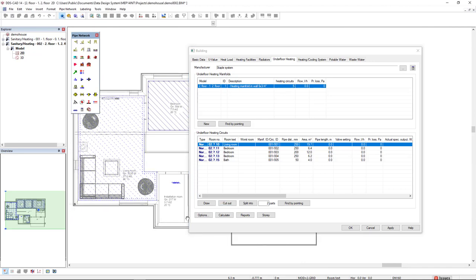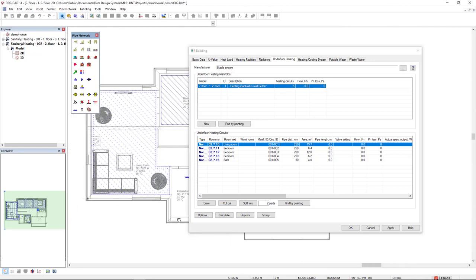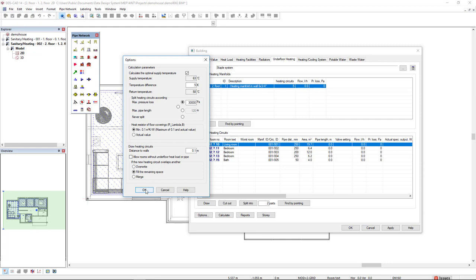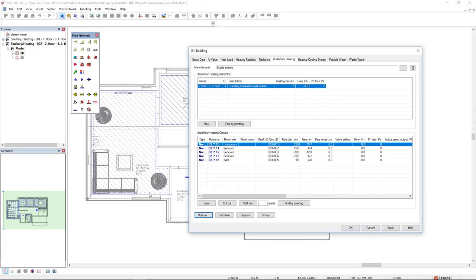Before we perform the calculation, let's see some options in the options button. We have the possibility to manually insert the supply temperature and temperature difference. But in this case, I will set DDS-CAD to calculate the optimal supply temperature by activating this option. We have all other options here that we could take into consideration. Click OK and I will click calculate.